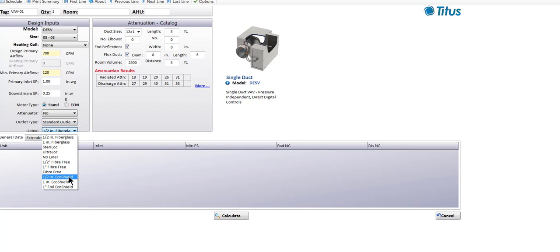Another lining option is EcoShield. This is unique for Titus because we have an exclusive contract to distribute this material in the HVAC industry. EcoShield is actually recycled cotton fiber — basically denim. When new blue jeans are cut out, the scrap material gets chemically processed to make it fire retardant and antimicrobial, then we permanently affix a facing. It's available in either a cloth facing called Lyshield or a scrim reinforced foil facing. The half inch thick EcoShield has an R value of 2, and the one inch thick EcoShield has an R value of 4.